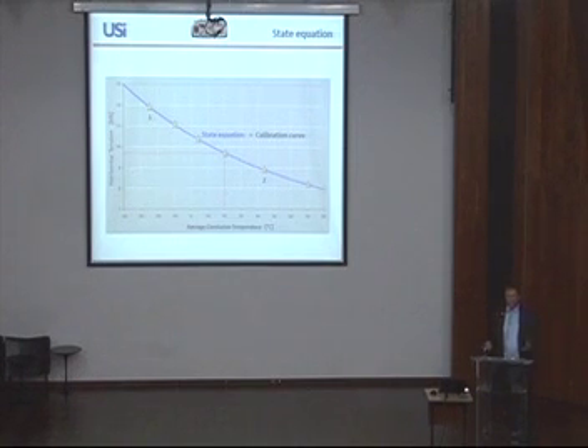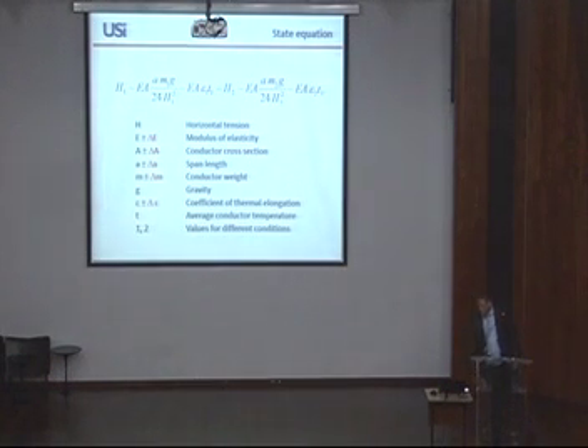So you would say, I know the relationship, you just showed me the formula. The problem number one is, all these parameters are not exactly known. So there are possible variations, maybe from manufacturing, like take the mass of a conductor, the conductor weight. It's allowed to vary to a certain amount during production. What does it mean for the calibration curve of a state equation if there's a small change in the weight of a conductor?